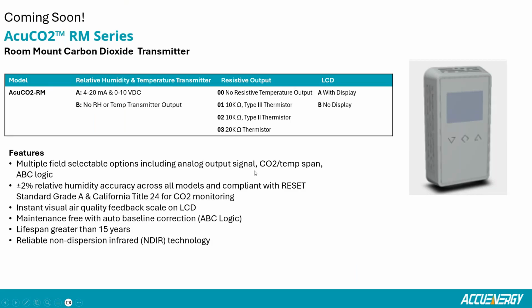One thing that I've been excited about is all the flexibility in the field to change features when you need it. So if you need to change the analog output signal for CO2, for temperature, for RH, if you need to change the temperature span, if you need to change the CO2 span, whatever the case may be, you'll be able to do that from the user interface on this unit.